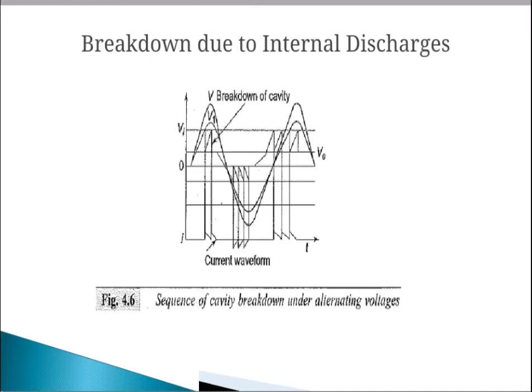When breakdown occurs in the void, electrons and positive ions are formed. Also, in each discharge there is some heat dissipation in the cavities, and this will carbonize the surface of the void and cause erosion of the material. Channels and pits formed on the cavity surface increase the conduction, and chemical degradation may also occur as a result of the active discharge products formed during the breakdown. This is the breakdown due to internal discharges.